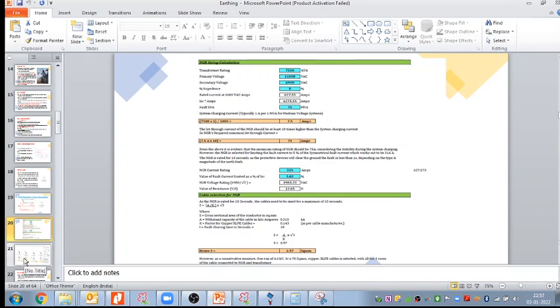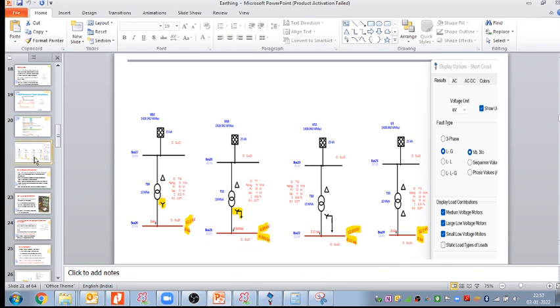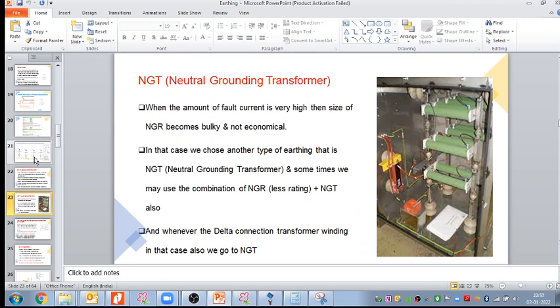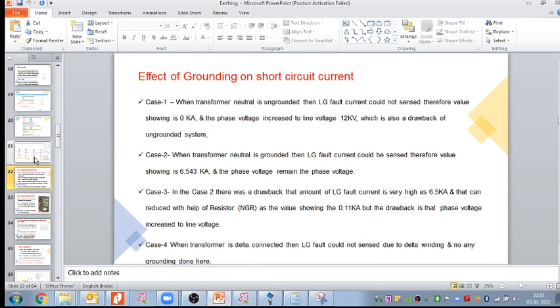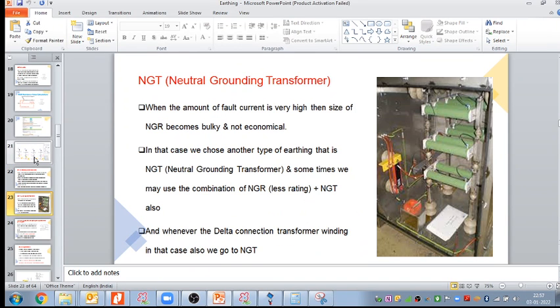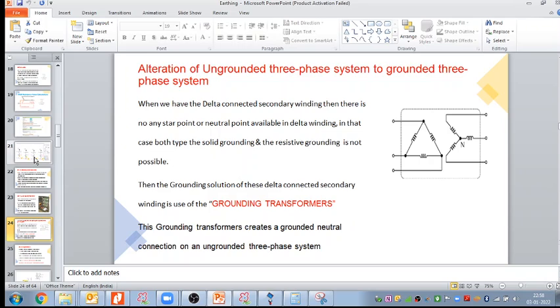There are a lot of things for grounding, and I don't think it is possible to complete them in one session. Again, the effect of grounding on short circuit current, NGT. A drawback of the NGR is that when we limit the fault current very much, the NGR will heat up. So heat is one problem with the NGR, and we have to think of an alternative to the NGR. So we go to the NGT, neutral grounding transformer, earthing and zigzag. Second, if the system is a delta connected system, how can we convert this ungrounded three-phase system to a grounded three-phase system? For that we have to use the grounding transformer.